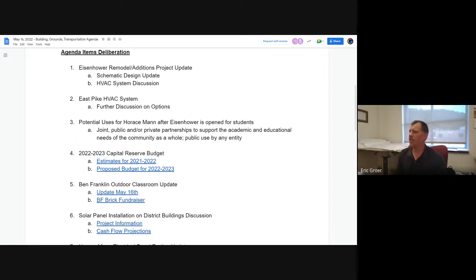The last option was geothermal. In this option, each classroom will get a water source heat pump, and there'd be a geothermal well field back where the asphalt currently is behind the school. We've estimated about 55 wells if we drilled about 500 feet deep. If we wanted to go to 250 foot depth, we'd have to double the amount of those wells. So the pro of this option is the least overall carbon footprint. My personal opinion is these are a lot more maintenance than options 1 through 4. Well, I'd say options 1 through 3.